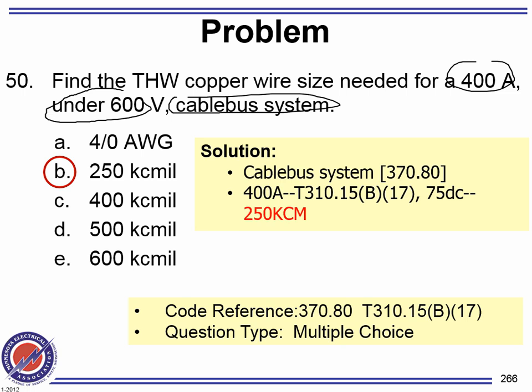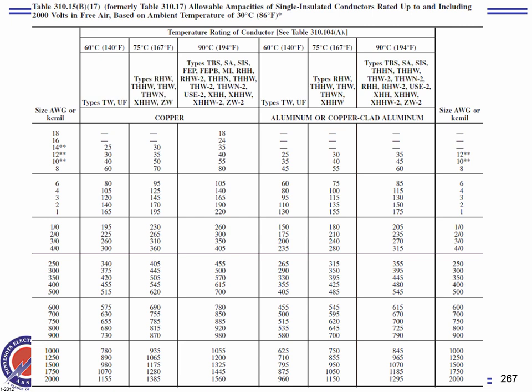All right, so for a 400 amp, I only need 250. Okay, here you go. So my equipment is 400 amp. I need the 75 degree column. Here's 400 amp. Can you see that? How much current do I need to carry? 250. Now, if you don't know that, where would you be going? You're going to be going to 310.15(B)(16). So make sure cable trays and cable busway systems are considered up in the air. They are like conductors in the air, and you don't use 310.15(B)(16). You use 310.15(B)(17) on them.